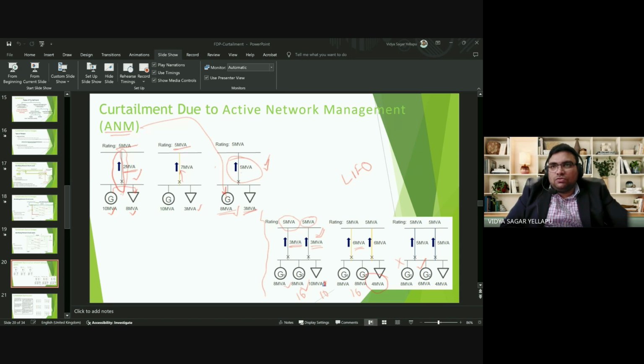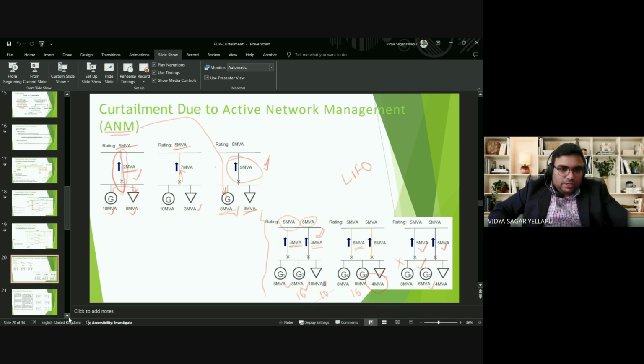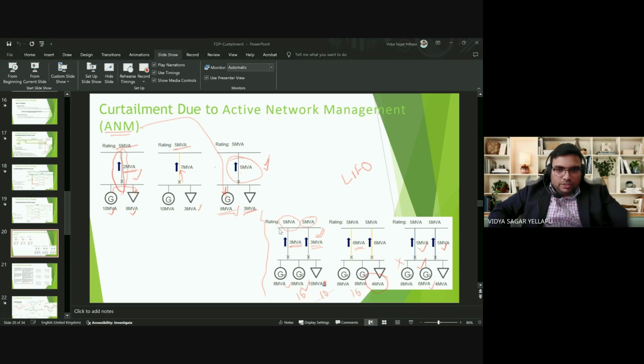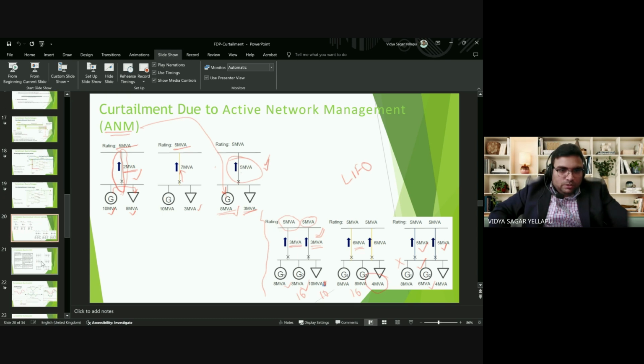and the allowable capacity is only 10 MVA. It has been given a signal to reduce the output. It is 6 MVA now, and it is now okay. This is an acceptable situation for the DNO, and the situation is solved. So in order to compute the energy reduction for a particular project, we need to consider all these things. What is the priority queue? We need to look at the priority queue of the generators and come to a figure for the estimation of curtailment.